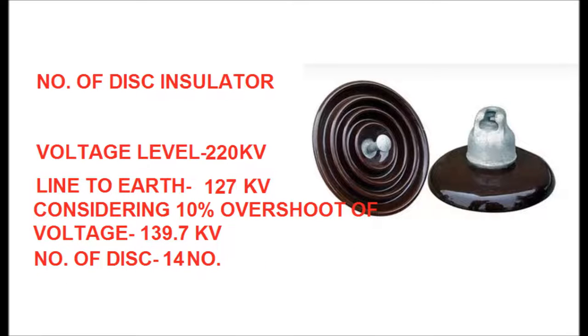For the 220 kV system, the line-to-line voltage is 220 kV. The line-to-earth voltage is 220 divided by √3, equal to 127 kV. Considering 10% overvoltage: 127 × 1.1 = 139.7 kV. Dividing 139.7 by 11 gives approximately 13. Adding 1 for safety margin gives 14 discs for suspension type string and 15 discs for tension type string in a 220 kV system.